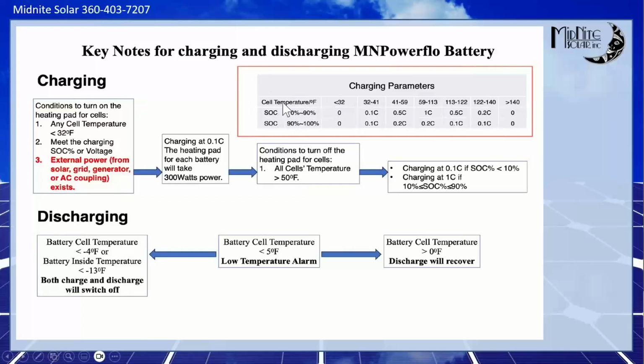This is missing a little part up here that is 0 to 10%. So it should be 0 to 10, 10 to 90, 90 to 100. So if the battery is below 10%, the battery will limit itself to 0.1 to 0.2 C charge rate based on the temperature. If the battery is between 10% and 90%, this is your charge rate based on cell temperature. So you can see if you're in the normal window here, you're going to have a 1C charge rate. And if the battery is above 90%, we throttle the charge current back again.